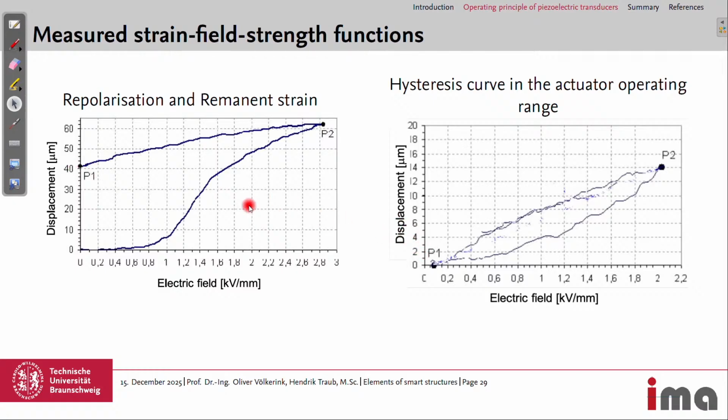And from this point on, we use this hysteresis, and there we won't go higher than 2 kilovolts to not change the polarization. Does this answer it? Further questions?